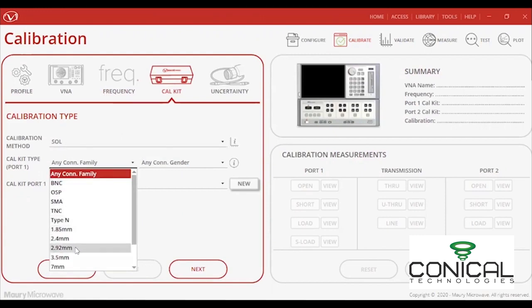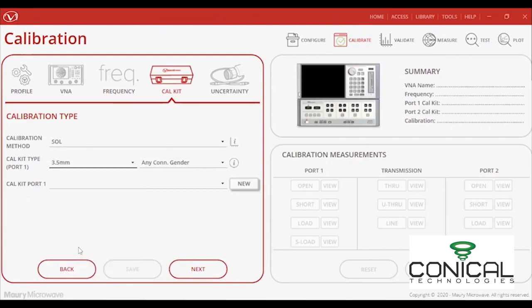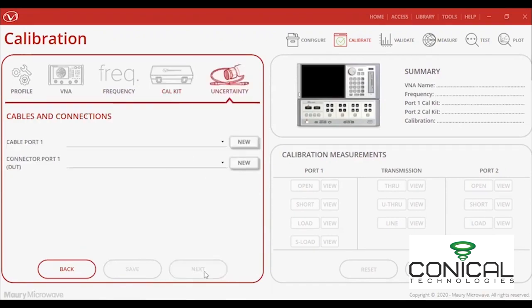As for the calibration methods, the list is also quite extensive and ranges from SOLT, TRL, LRM, and you can even perform on-wafer calibrations. In my case, I chose to go with the one-port SOL calibration method using the characterized CalKit, which will also empower measuring S parameters with uncertainty. Once my calibration method is set, I can proceed on to setting up the cable and connector uncertainties in the next tab.